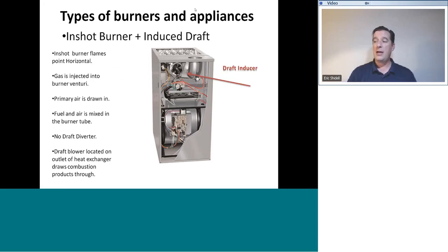On a furnace like this, the draft inducer is located on the outlet of the heat exchanger. In this cutaway example, the burners are down here shooting into the heat exchanger. The fan is pulling on that heat exchanger, pulling those products of combustion through. So this heat exchanger also operates under negative pressure, as does the heat exchanger on the natural draft furnace. It's just that now we have a fan to pull those combustion products through. Hence the name inducer. It induces.